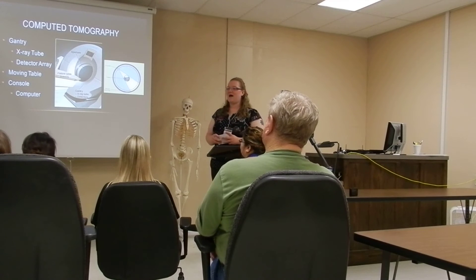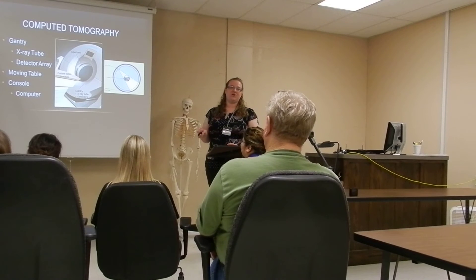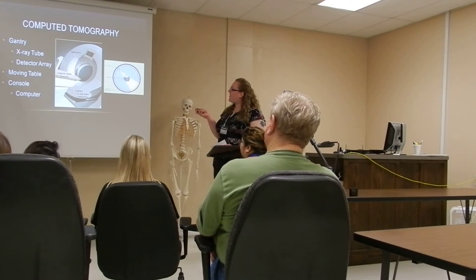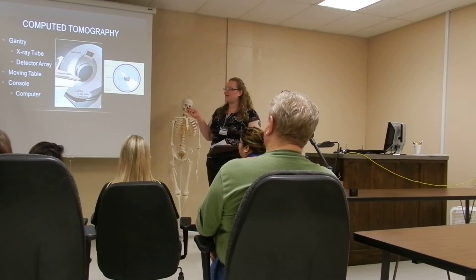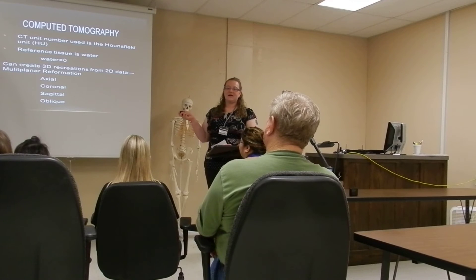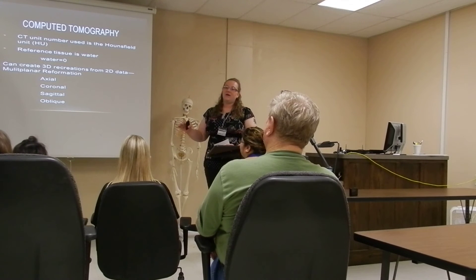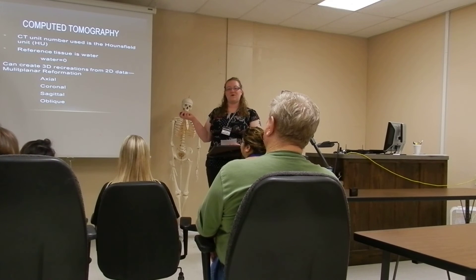Computed tomography is considered the gold standard for this imaging. CT has a gantry housing the x-ray tube and detector array, a patient couch that moves the patient in and out, and a console for post-processing. The patient lies stationary while the couch moves them and the x-ray tube rotates around them. CT uses Hounsfield units to describe how different tissues attenuate x-rays. Water is the reference at 0; higher values appear lighter gray to white, and below 0 appears darker gray to black. CT can also create 3D images from 2D slices.